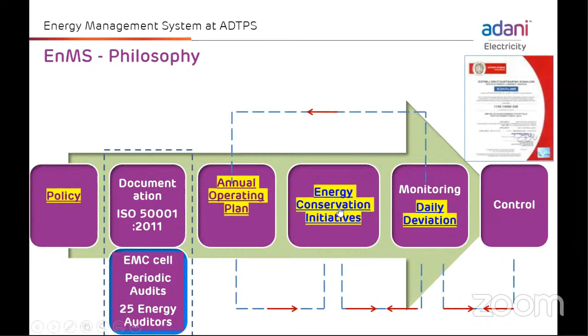I will show one example. This is the improvement plan taken by one department, the operation department, to reduce the auxiliary power consumption of the boiler feed pump by reducing the slip losses of the hydraulic coupling by 5 to 7%. Every department has to take such initiative or improvement plans so as to reduce energy consumption and achieve the annual targets of AOP.